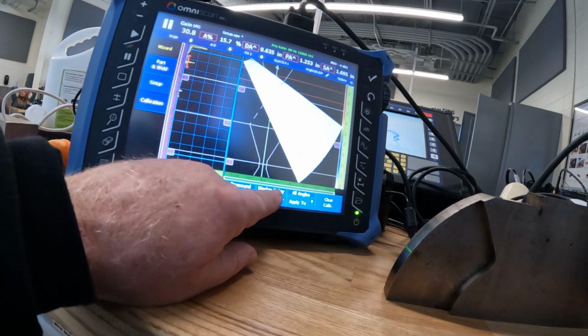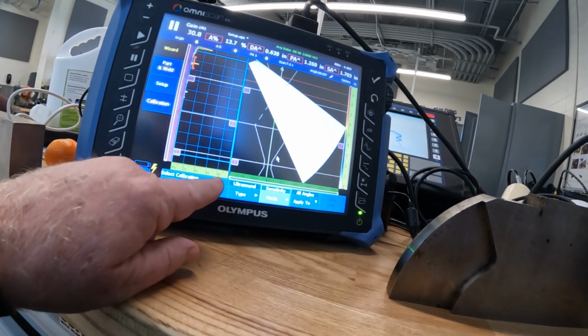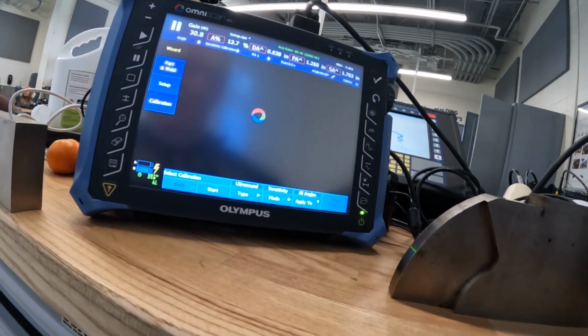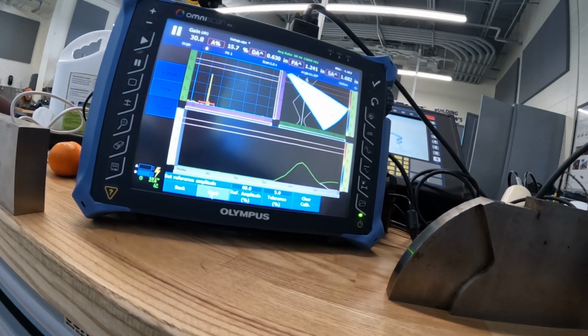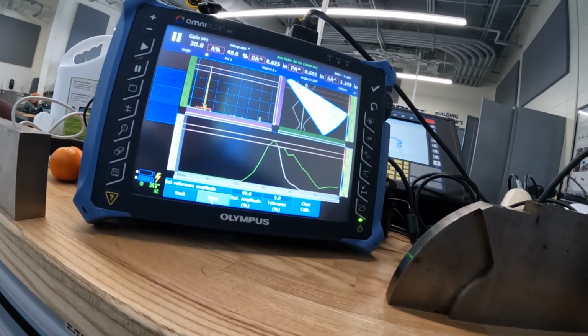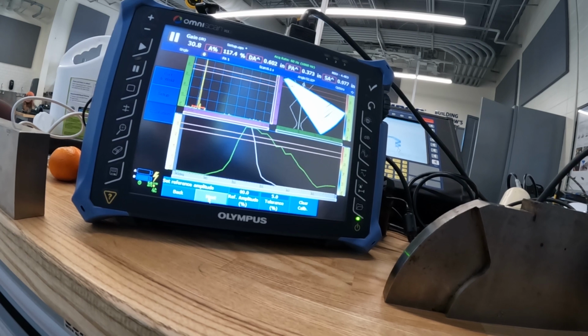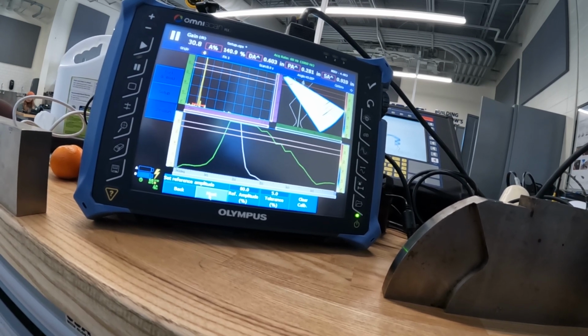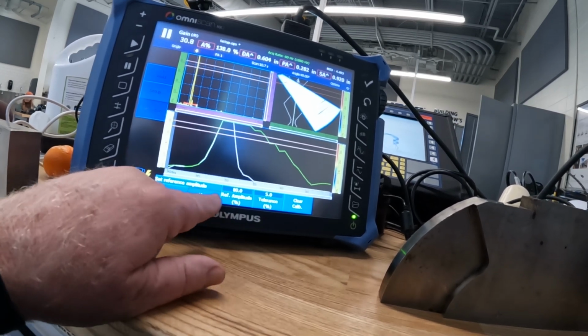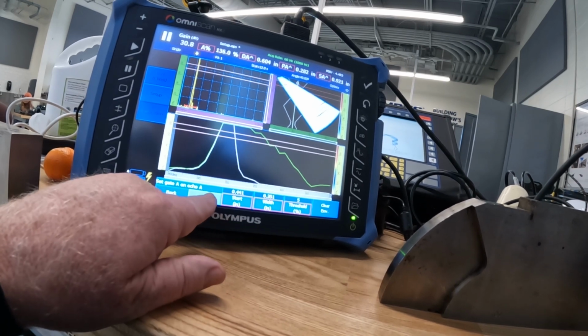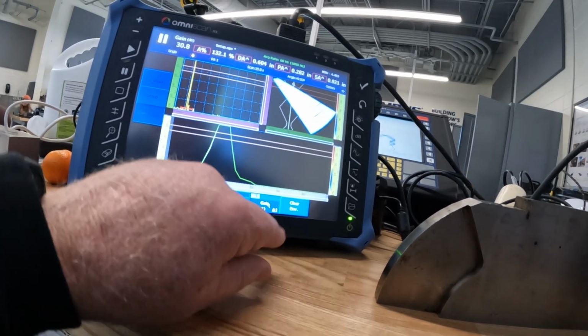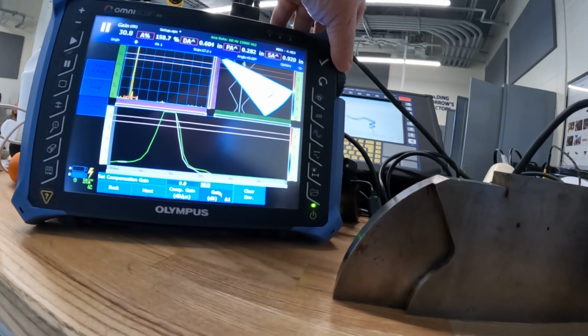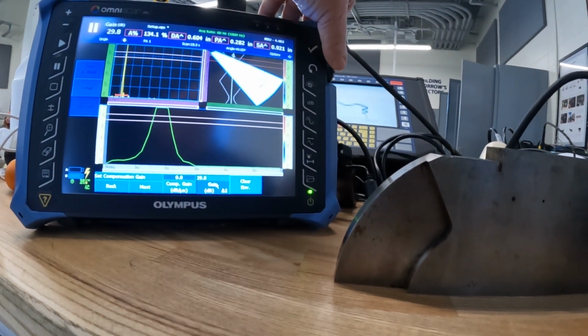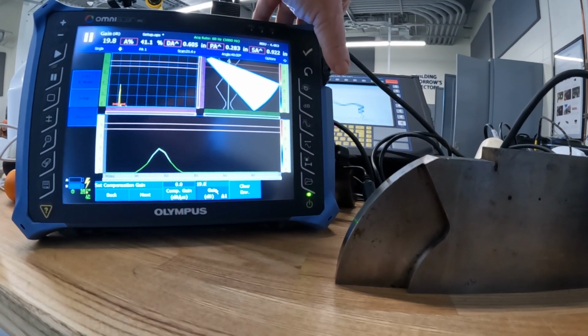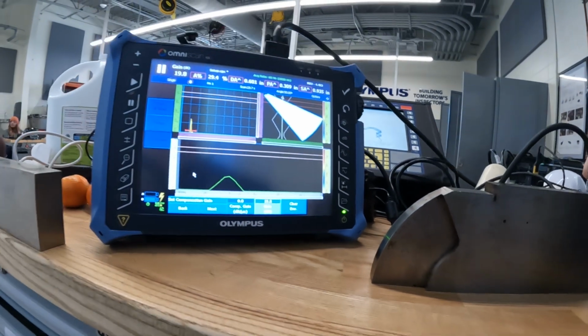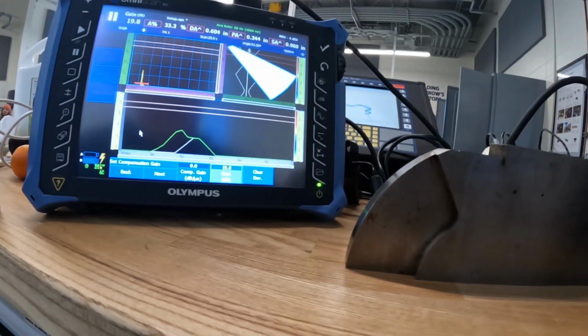So the next one is sensitivity. This is the one you love so much. Okay. So again, for sensitivity, I'm already in the right spot. I'll notice as I'm going across, you see where my amplitude is on my response? I mean, my gain is too high. So I'm going over to where it has my gain control. I'm going to turn it down to where my signal is about 50%. So I'm going to work at that point on 50%. Let's see if I can get a calibration.